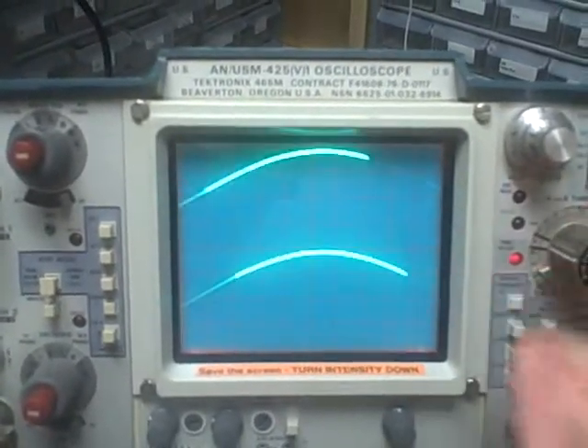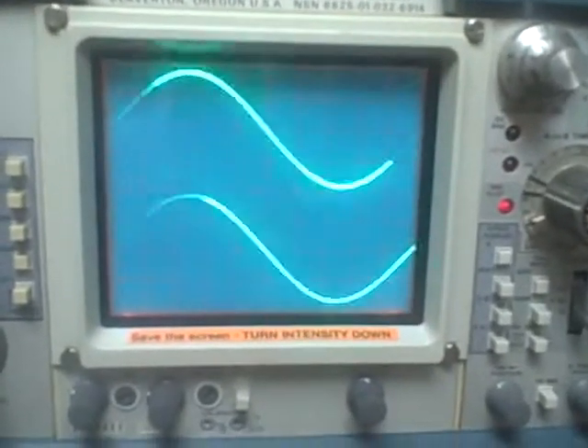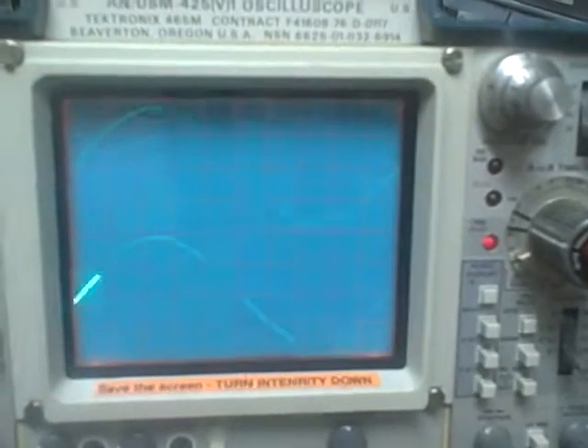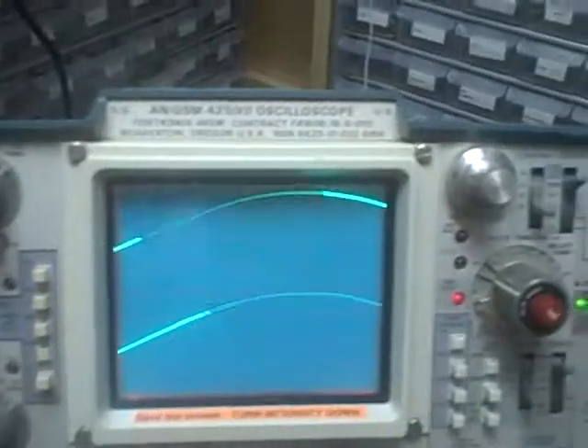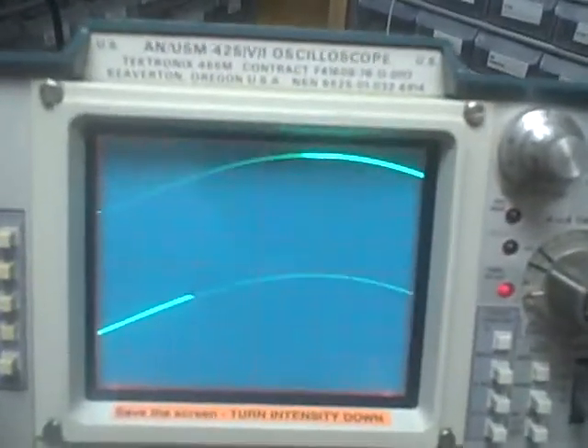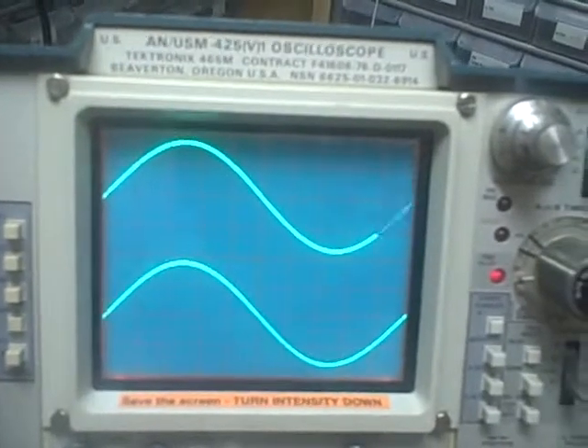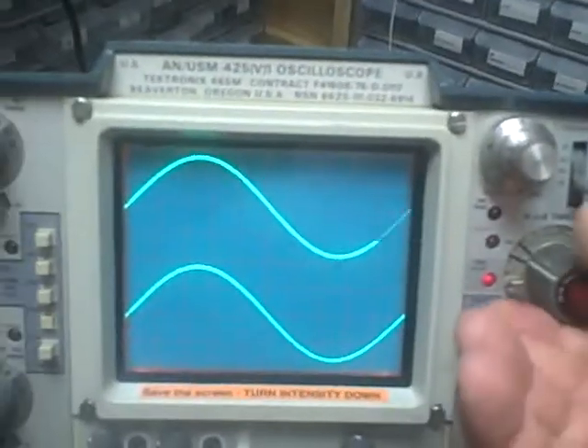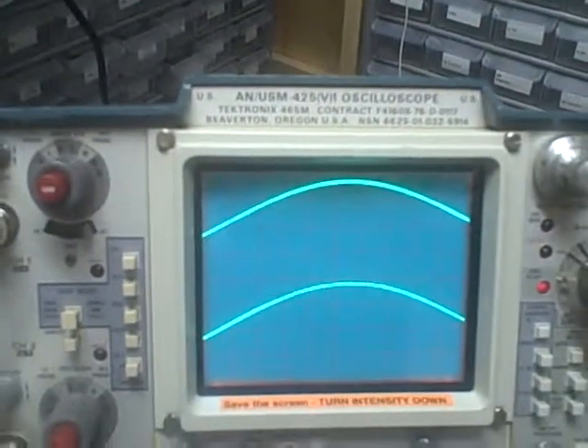Now if I go to 5 milliseconds, I should be able to turn my time base up to 20. And there we are again, in calibration. If I go to 2 milliseconds, I should be able to go to 50. There we are again. 1 millisecond — should be able to go to 100.